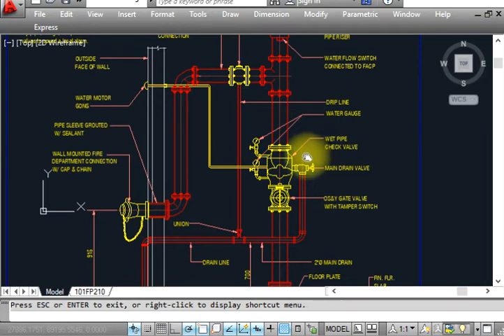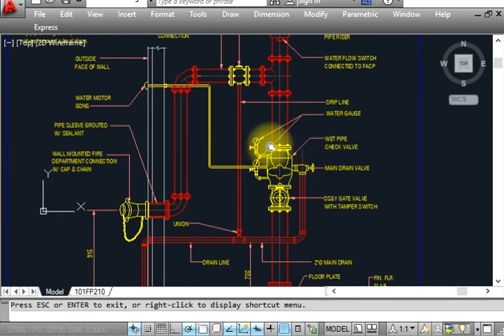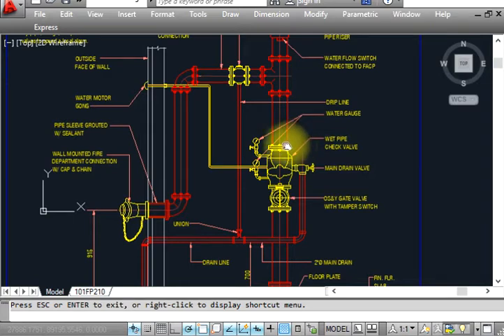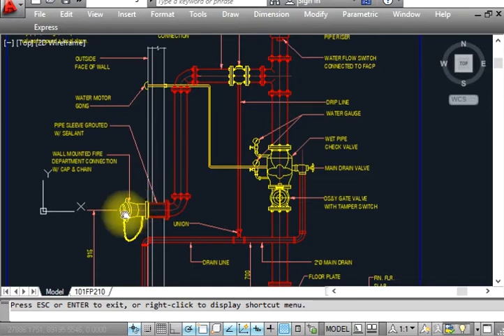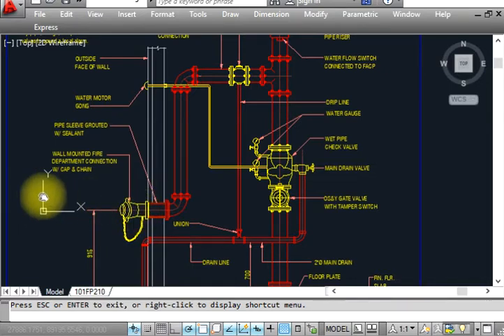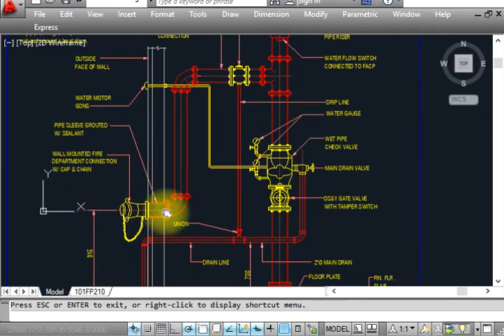In case of failure of the system, if electricity and electric-driven pump and diesel pump are not working and water is finished, the siamese connection will be used by the fire truck. The fire truck will come and connect to the siamese connection.